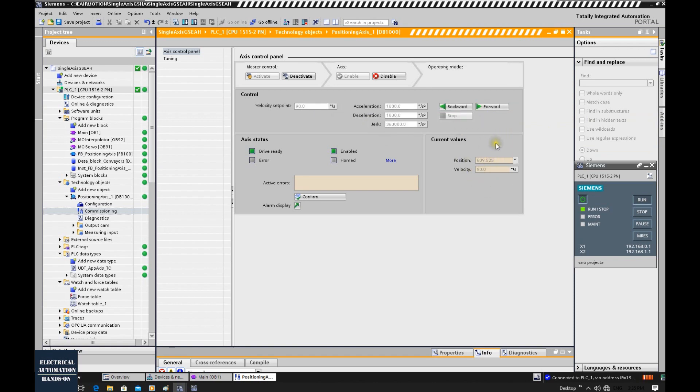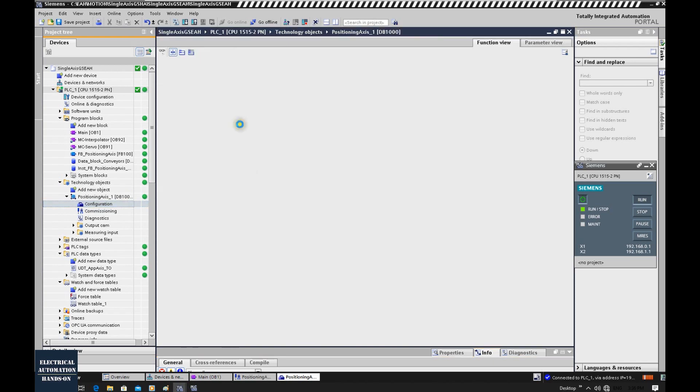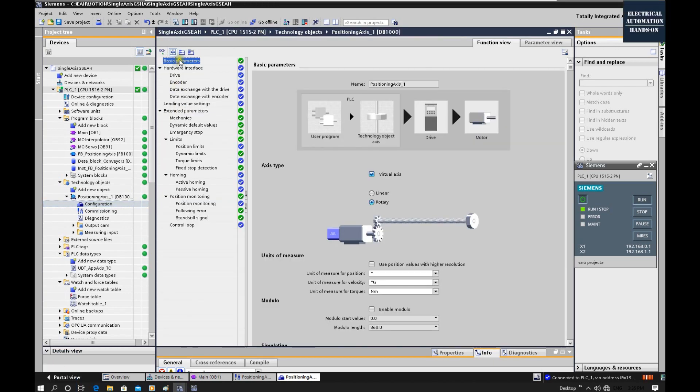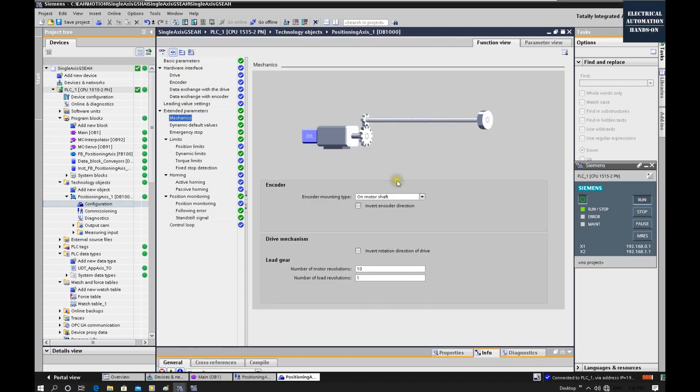Click stop. Using this way, we can verify if the forward or backward match our direction. If it doesn't match, we can go to the configuration, go to the TO setting and find out the mechanics, and we can check this invert rotary direction of the drive or invert the encoder direction.